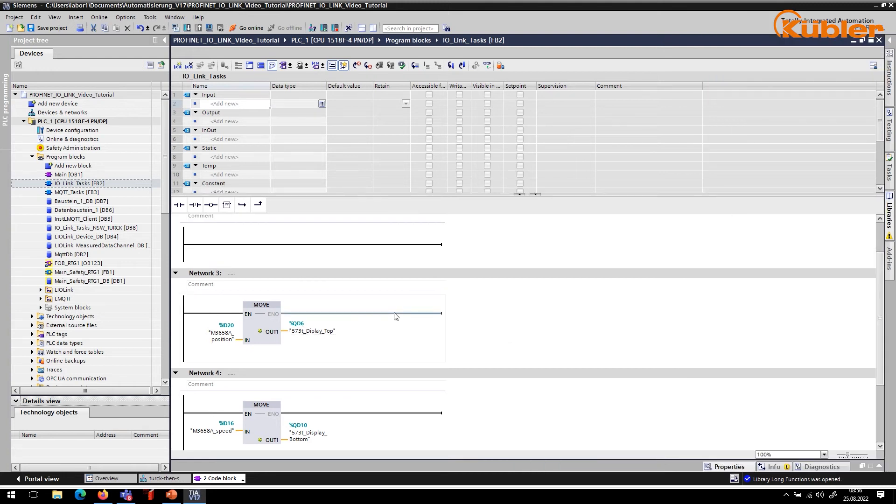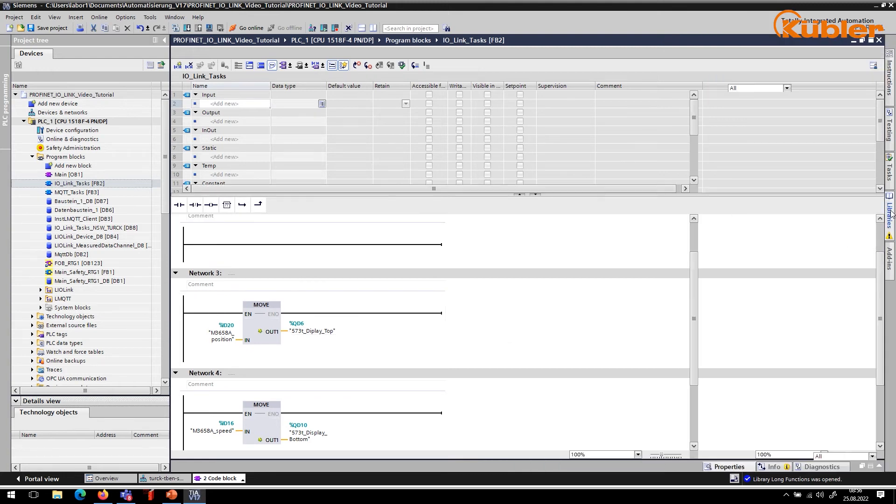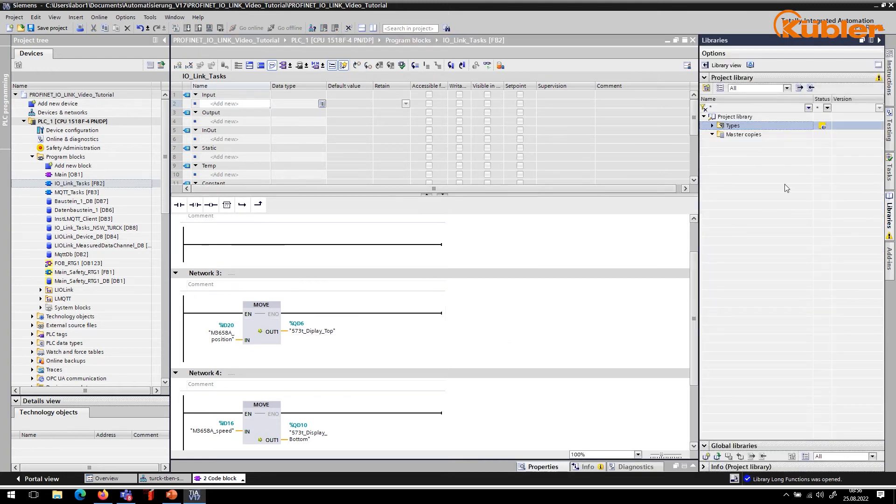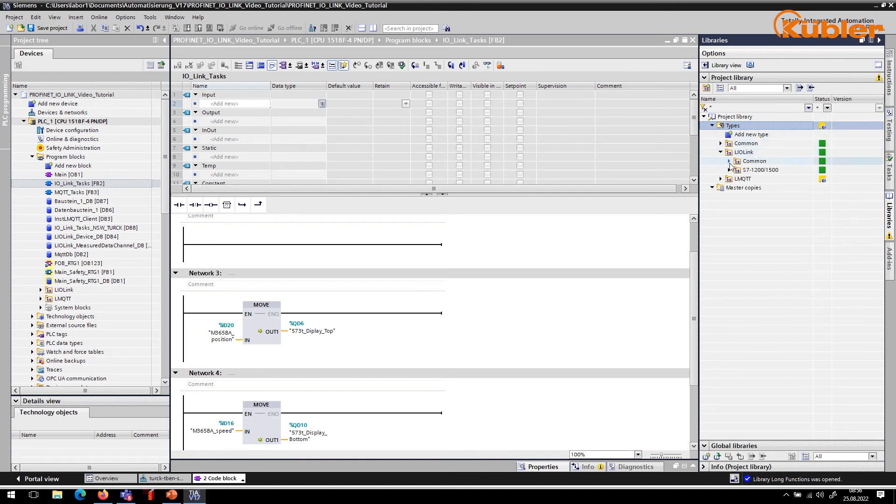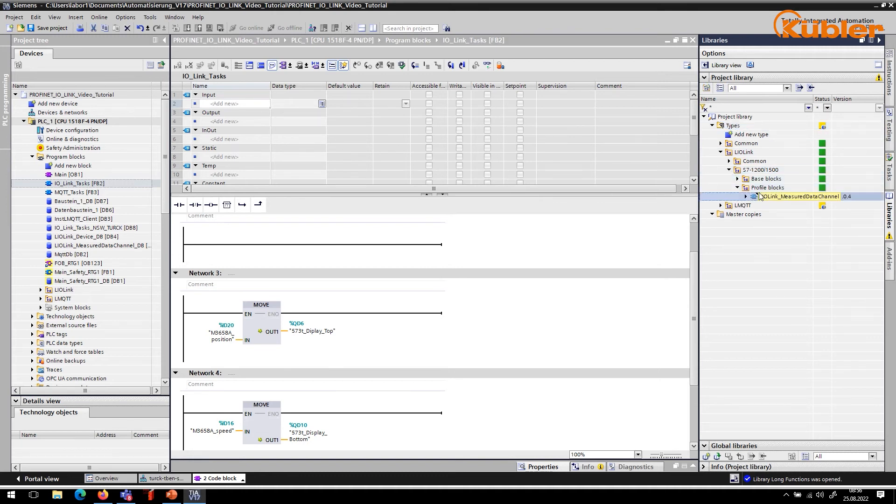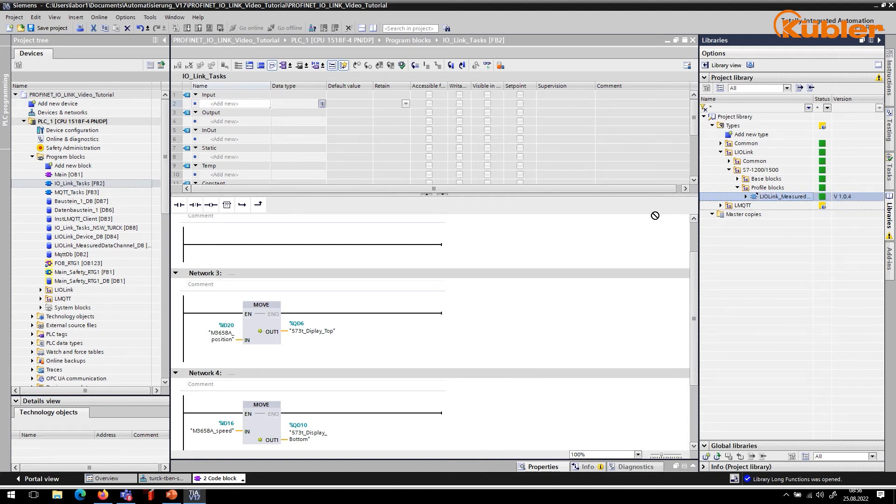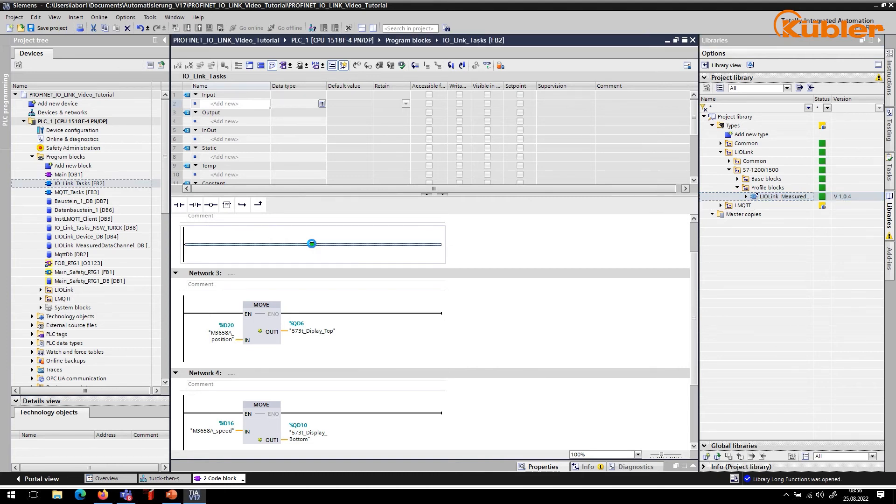As soon as the smart sensor profile is used, a scaling can also be applied for the actual measured value. To calculate the scaled position, the block LIO-Link measured data channel is required. This function block can be found in the library Common and Smart Sensor Profiles and is available for download on the Siemens webpage. Siemens provides a suitable function block in the TIA portal for each Smart Sensor Profile class.